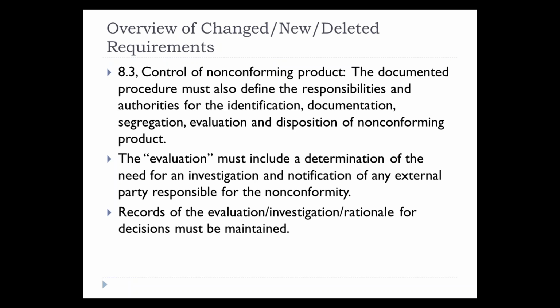(8.3) Control of non-conforming product. Nothing new here. You need to have a documented procedure, but it needs to define the responsibilities and authority for identification, documentation, segregation, evaluation, and disposition of non-conforming product. The evaluation needs to include a determination of the need for an investigation and notification of any external party responsible for the nonconformity, and records of your evaluation, investigation, and rationale for any decisions have to be maintained.